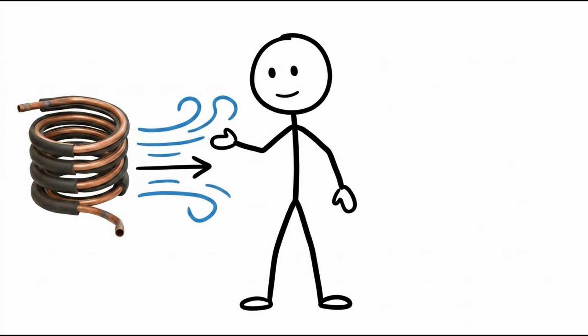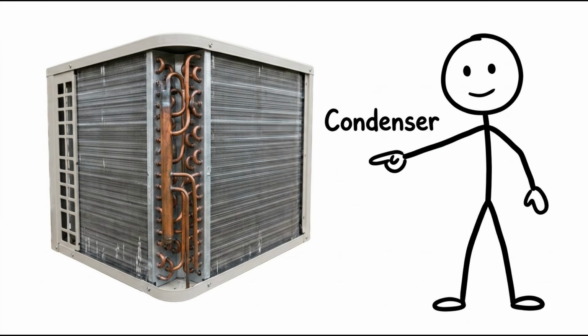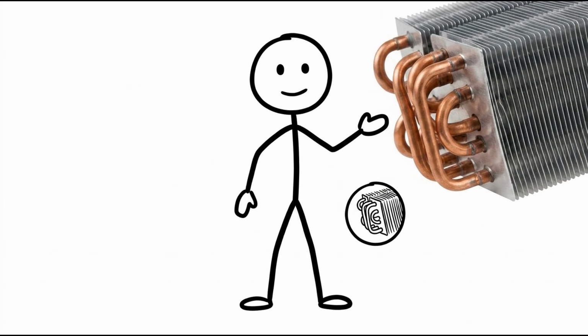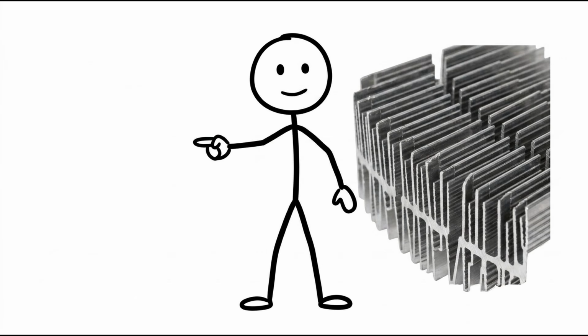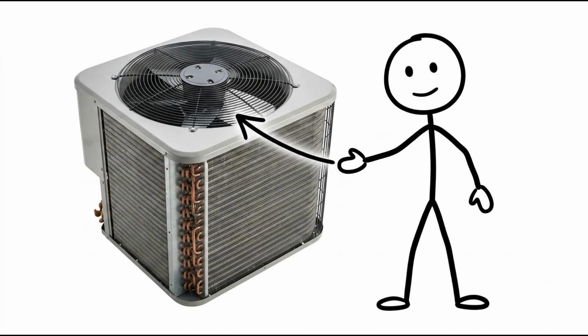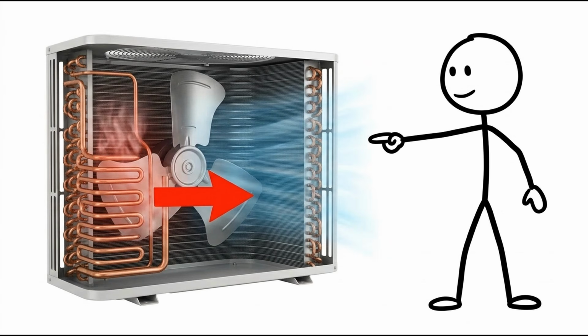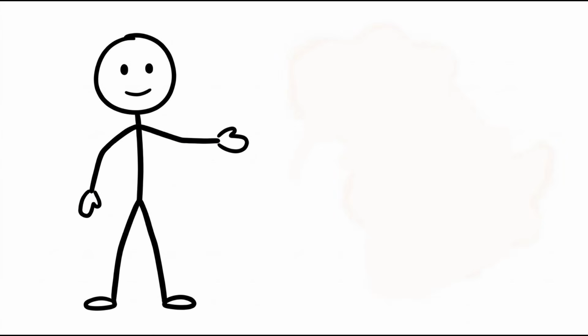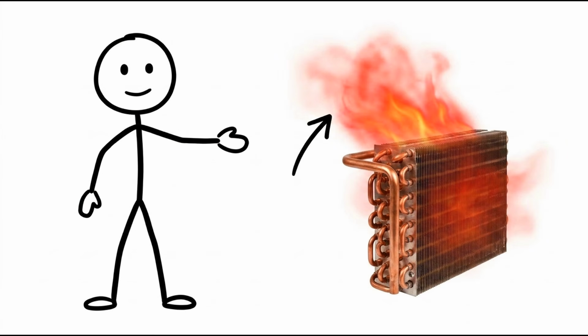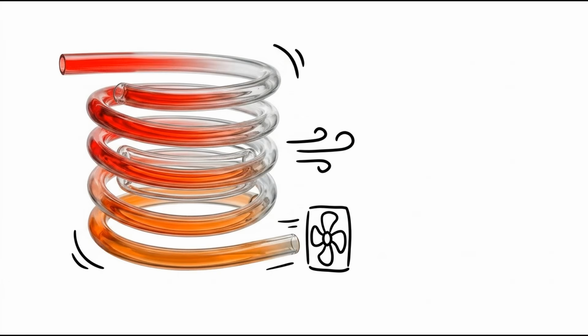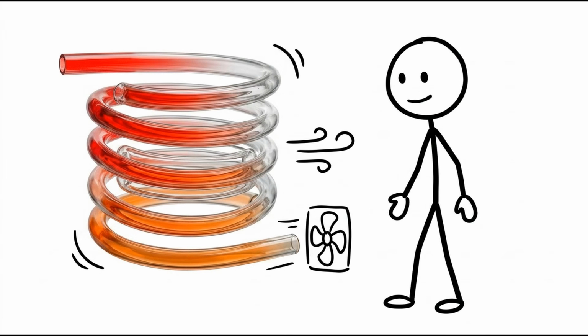The hot, high-pressure refrigerant now flows into another coil located inside the outdoor unit. This second coil is known as the condenser. Large aluminum fins surround the tubing to increase the surface area available for heat transfer. A powerful outdoor fan continuously pulls outside air across the condenser coil. Because the refrigerant is now much hotter than the surrounding outdoor air, heat naturally begins leaving the refrigerant and entering the atmosphere. As more heat escapes, the refrigerant gradually cools.